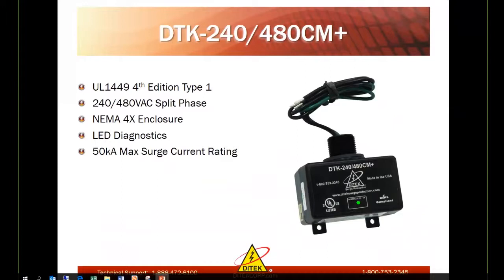The DTK-240/480CM+, also featured on the same data sheet as the 120/240CM+, is a UL 1449 4th edition Type 1. It is a split phase 240/480, typically for lighting panels. Perfect for lighting panels. That's basically why we did create it, but it will protect on any split phase 240/480 application. NEMA 4X enclosure, 50 kA with diagnostic.